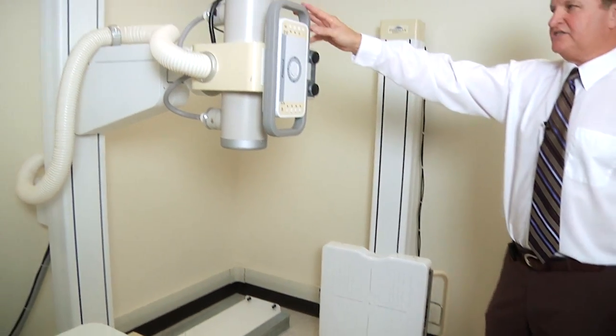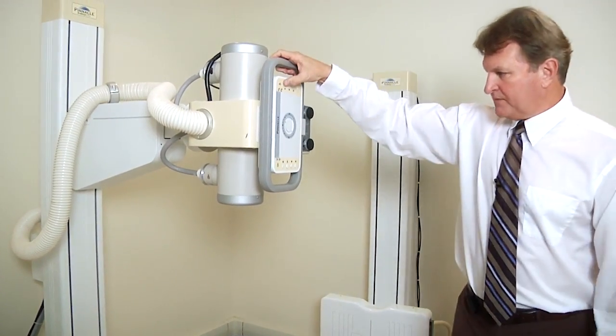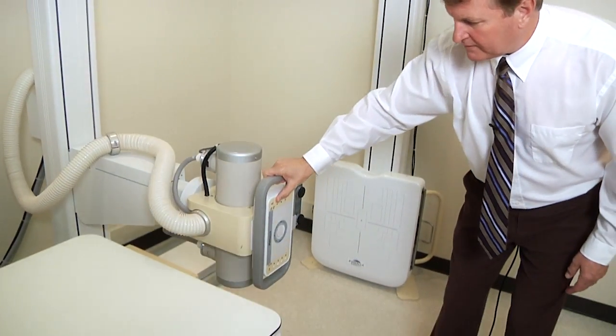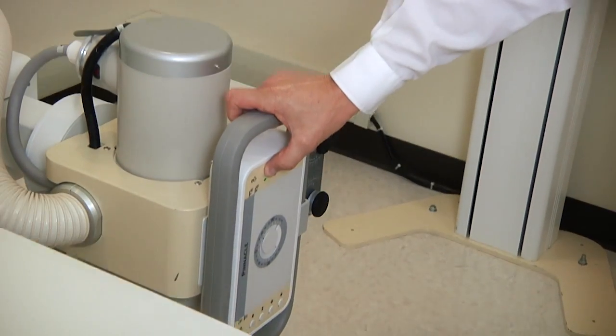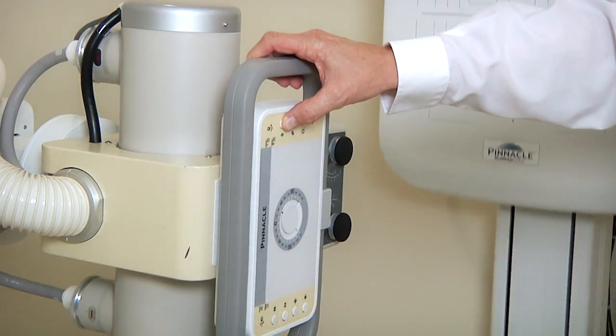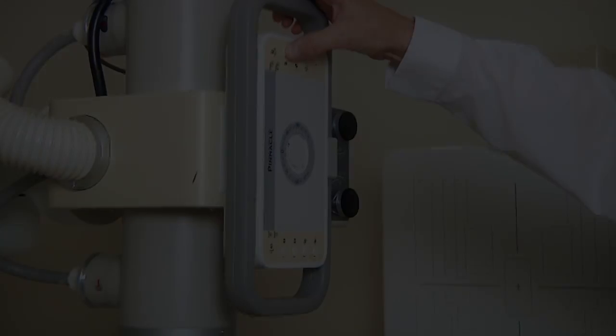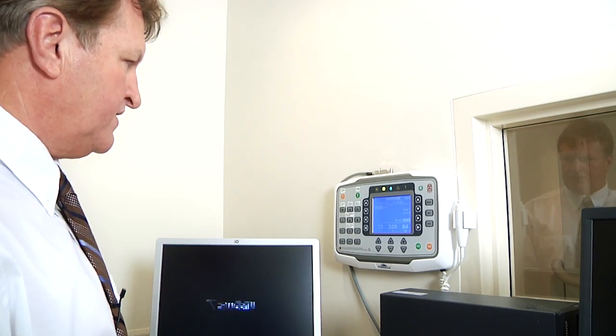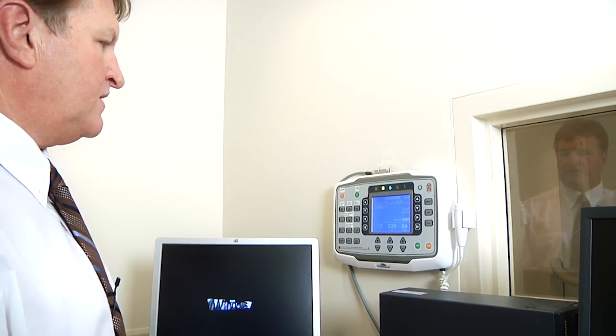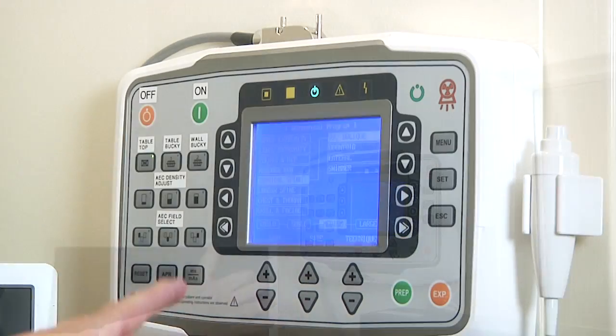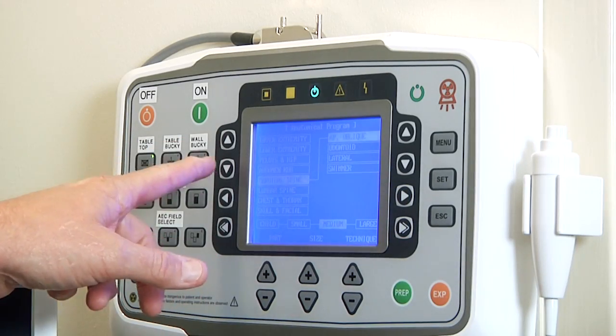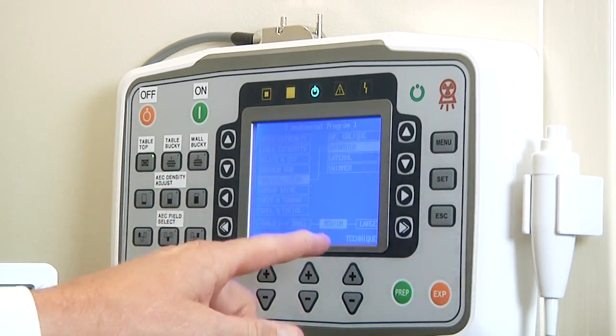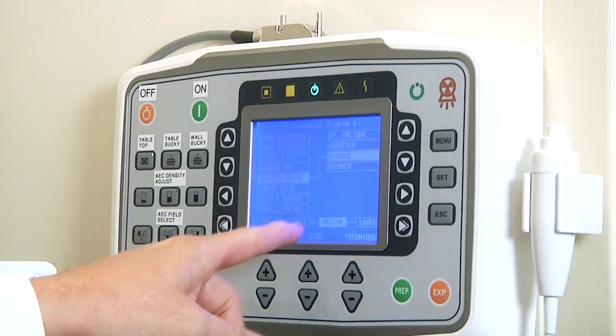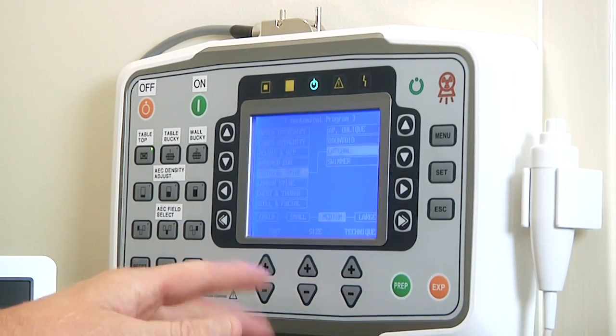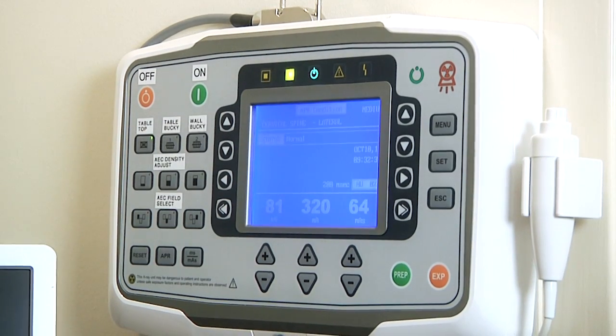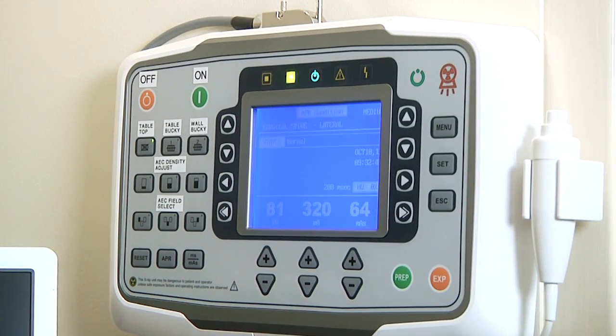The tube stand has the same amount of vertical transport for complete imaging. The operator's console is very intuitive, and the 32 to 82 kW all have the same look. To select a study, you would pick the body region, the particular view with the up and down arrows, small, medium, large, or centimeter size of the patient. Select the start button. The exposure is ready.